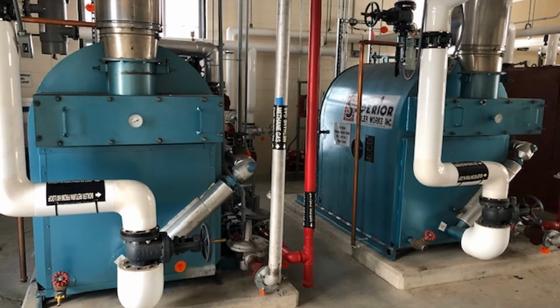The 2 supplemental boilers are dual fuel, meaning they can run off the methane produced from the digesters, or they could also run off natural gas if needed. Ideally, these units do not operate and are only here in case of an emergency or if we had one of our combined heat and power units down.